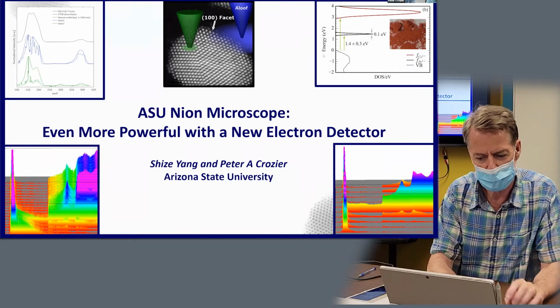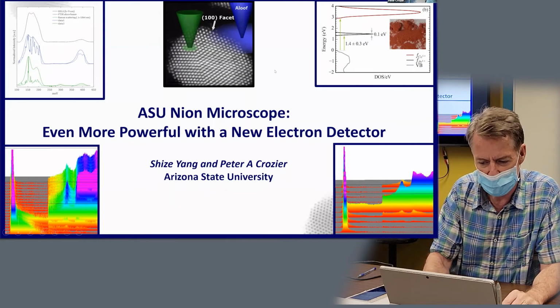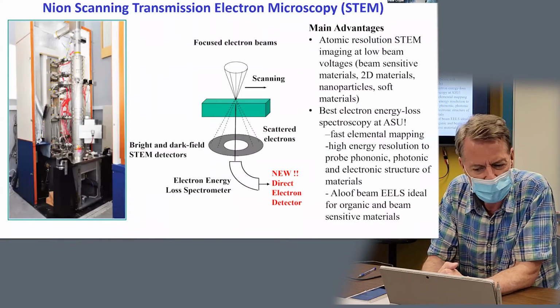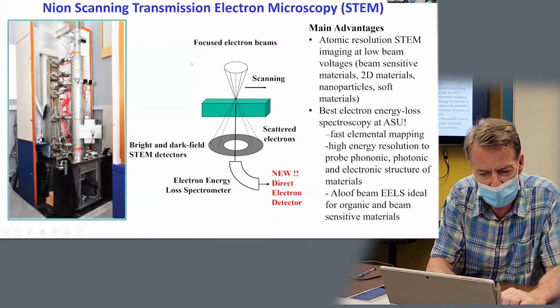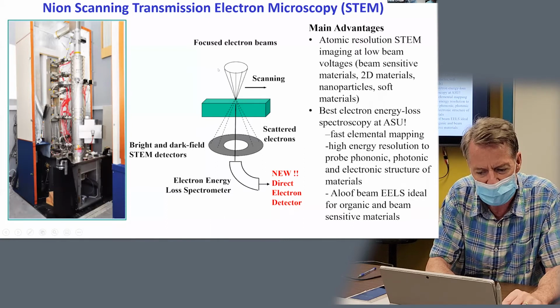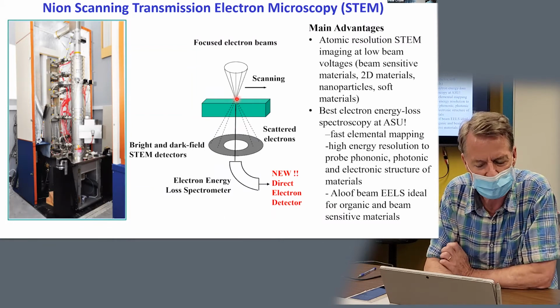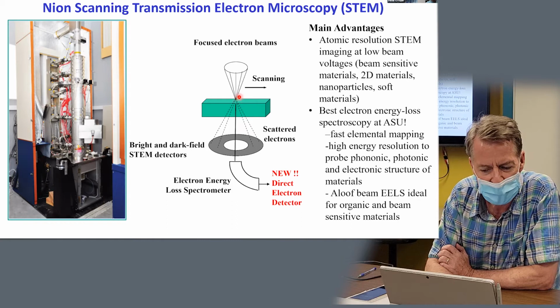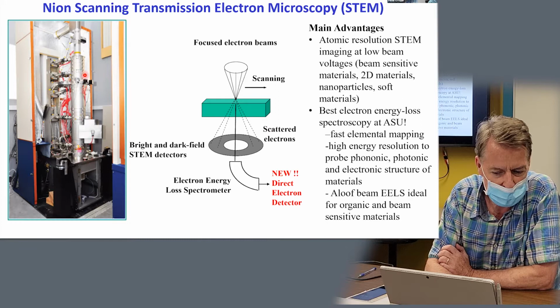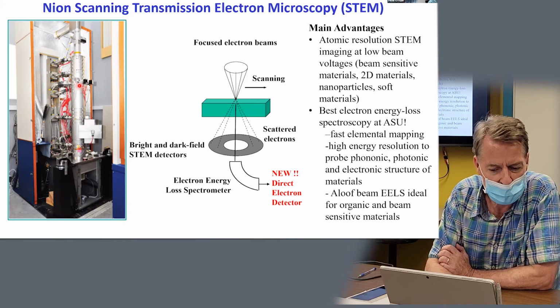The Nion Microscope, for those of you that might not be so familiar with it, is a scanning transmission electron microscope. The idea is that the electron beam is focused down to a small spot, typically 1 angstrom in size, about the dimensions of an atom, and then we scan the beam over the sample and collect the scattered electrons to form images or diffraction patterns. And this is a photograph of the microscope over here. You're welcome to come and look at it in the Eyring Material Center whenever you want.